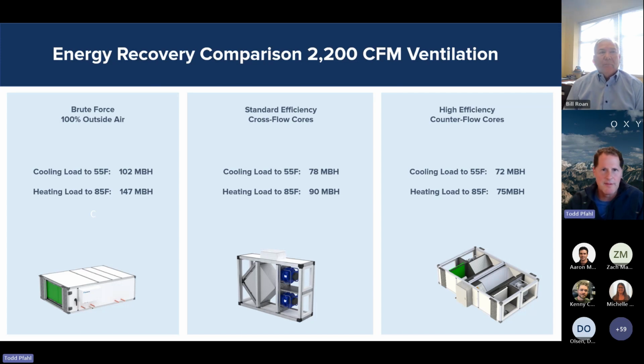If we just use a standard efficiency core, we can reduce that cooling load by 20% and the heating load by 40%. And then again, using our high efficiency counterflow cores, now we're reducing your cooling load by 30% and your heating load by 50%. So again, reduce the first cost of the building. We don't have to deal with the amount of outside air load that we typically would have. And obviously the smaller equipment also runs more efficiently over time.